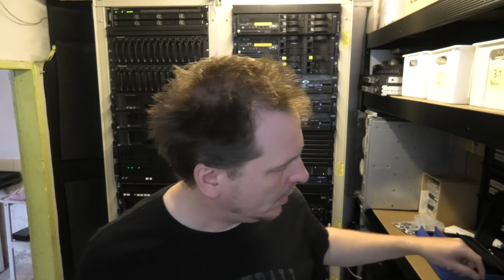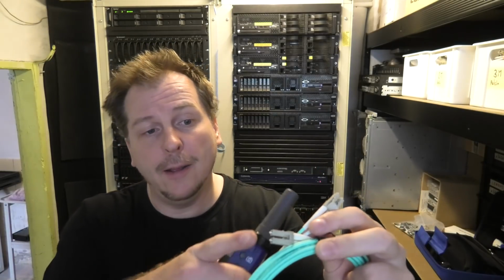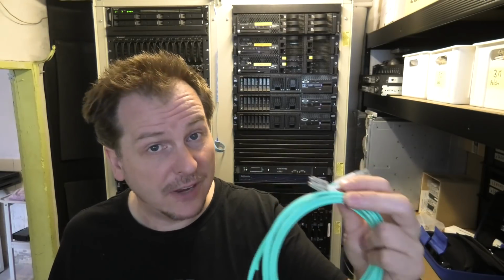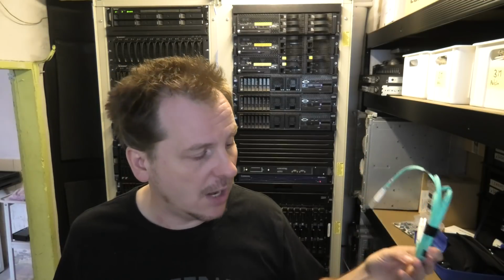What we found with this little microscope was that 24 out of 25 cables failed, and not just a little bit. On a cable you have 2 connections here, 2 connections there, so each cable has 4 connections. 25 cables, that's 100 connections really, and the test failed on 49 out of 100. That means there was more than 1 error on each cable, almost 2 errors on each cable, which can probably explain why we have been battling so many errors on our fiber optic network.